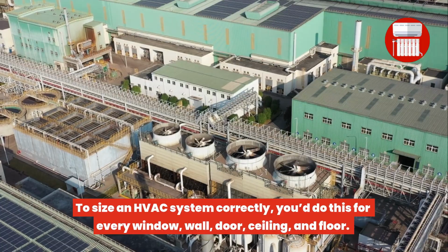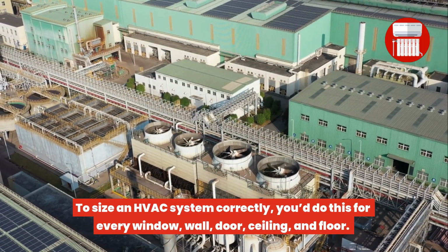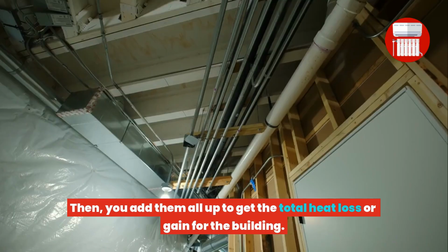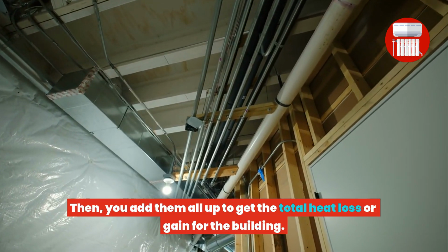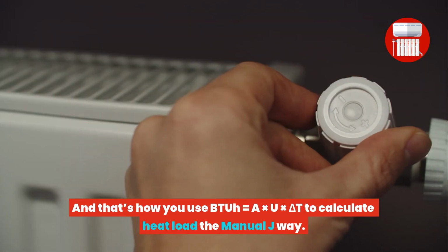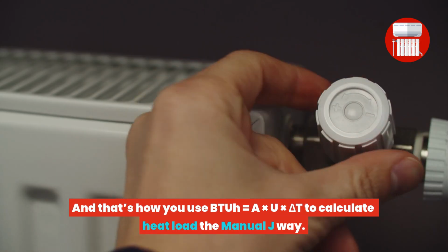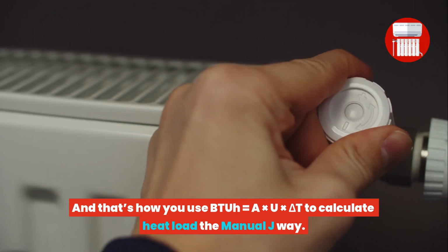To size an HVAC system correctly, you do this for every window, wall, door, ceiling, and floor. Then, you add them all up to get the total heat loss or gain for the building. And that's how you use BTU = A × U × ΔT to calculate heat load the Manual J way.